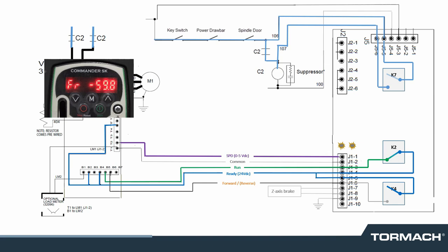A similar circuit on the machine control board sends 24 volts DC back to the VFD through the closed contacts of relay K4, connected to J1-5 and J1-6 as the forward reverse signal. When present, the spindle drives forward. When absent, the spindle reverses. The VFD display will include a minus symbol with the frequency and speed when spindle reverse is desired.